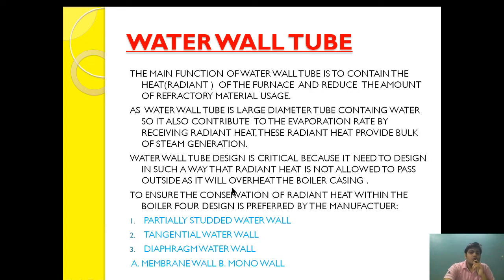The main function of a water wall tube is to contain the radiant heat of the furnace and reduce the amount of refractory material used. The water wall tube is large in diameter and contains water, so it also contributes to the evaporation rate by receiving radiant heat.